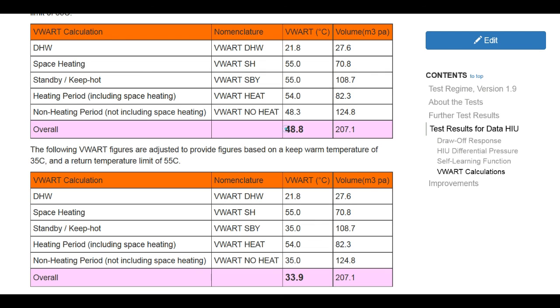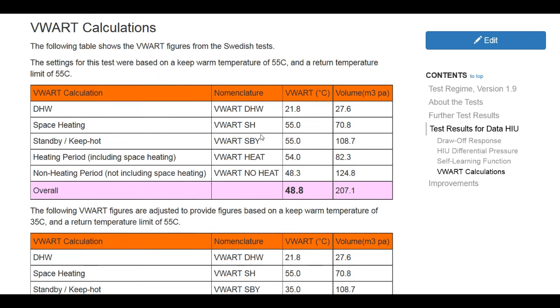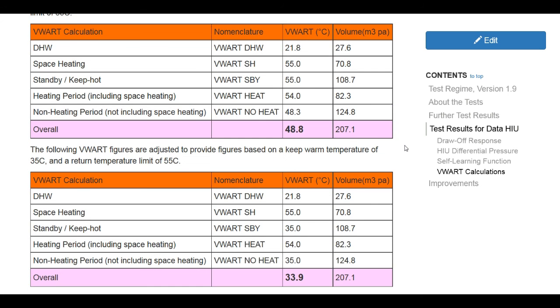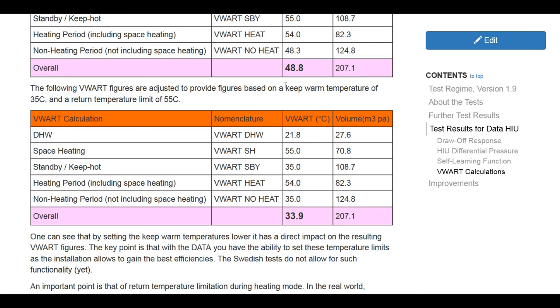Now, the first table here shows the test results with the keep warm temperature at 55 degrees C. So that's maintaining water in the heat exchanger at set point. Now, it's normal in installations to drop the keep warm set point to something in the region of 45 or 35 degrees C. Now, the effect of this can be shown in the second table here, where the VWART calculation would drop to in the region of 33, 34 degrees C.